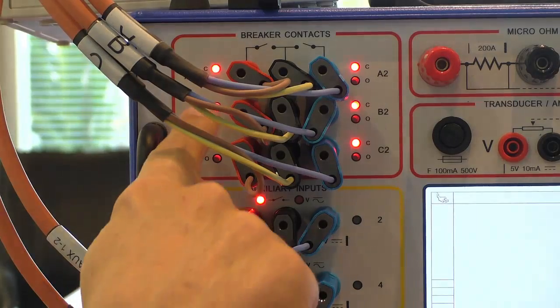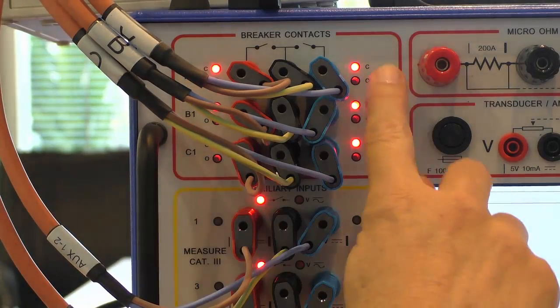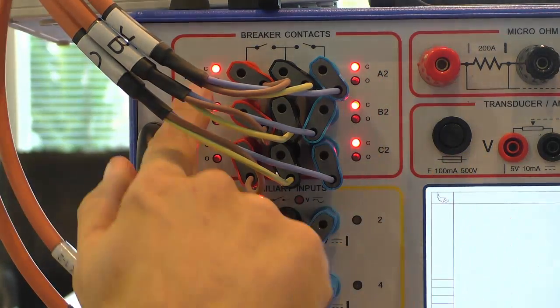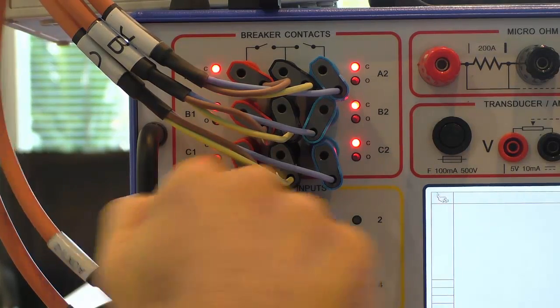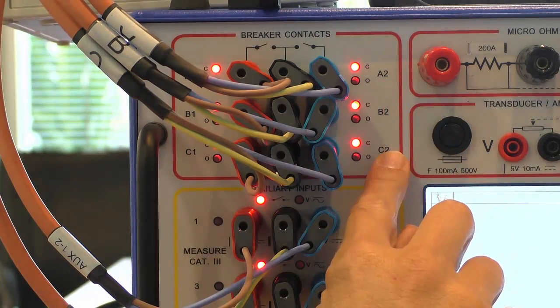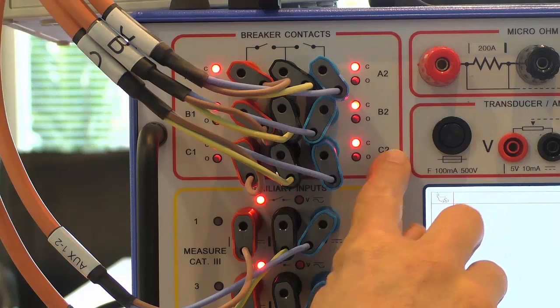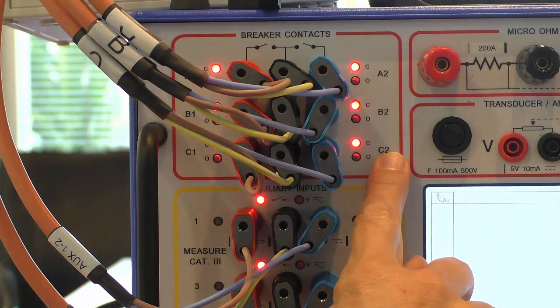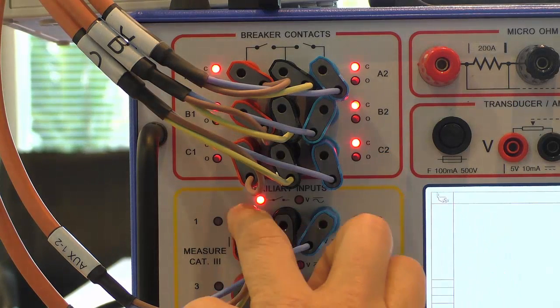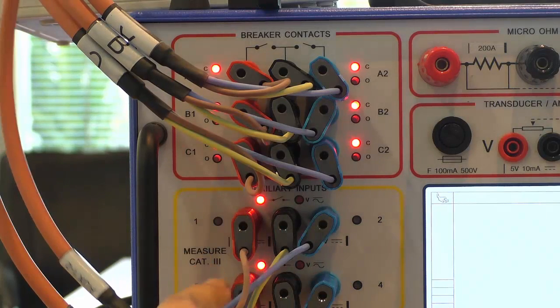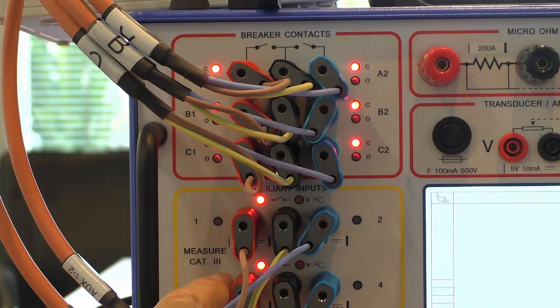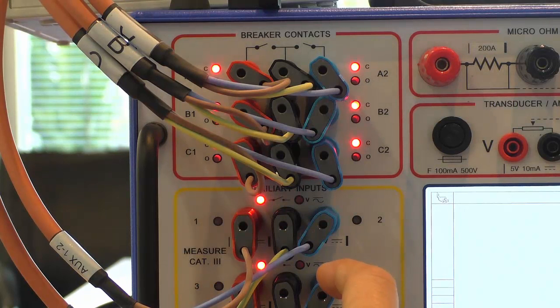As you can see on the main contact timing, both the A, B, C, A1 and A2, B2 and C2 are all red, indicating that the circuit breaker main contact is in the closed position. We can also see that some of the auxiliary contacts are in the closed position and others are in the open position.